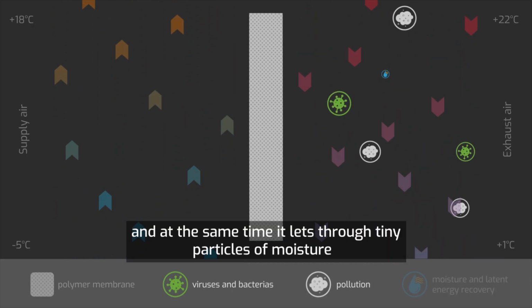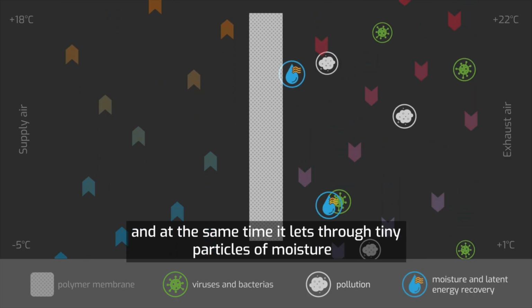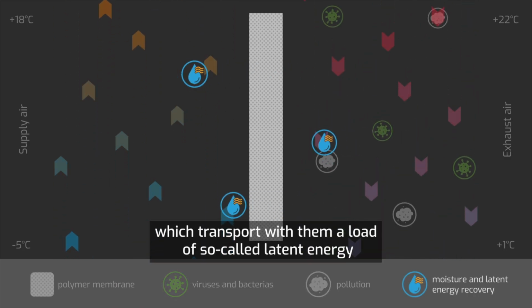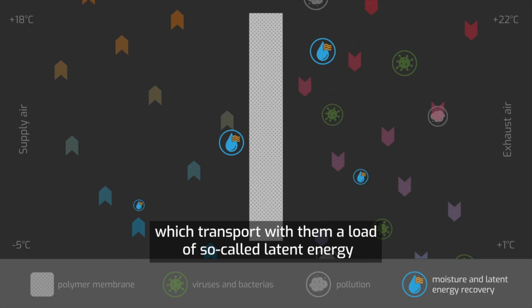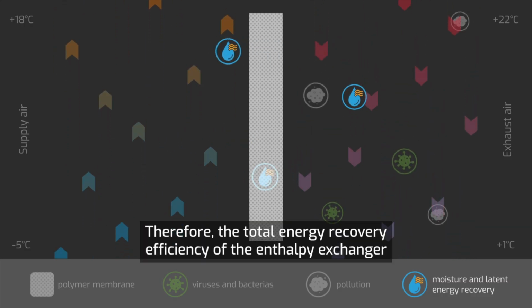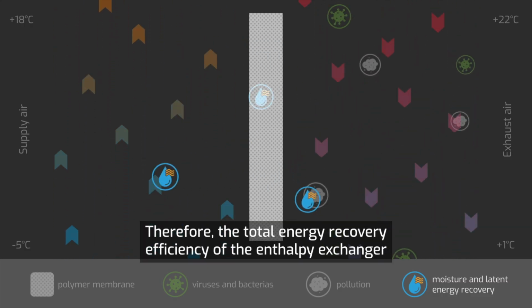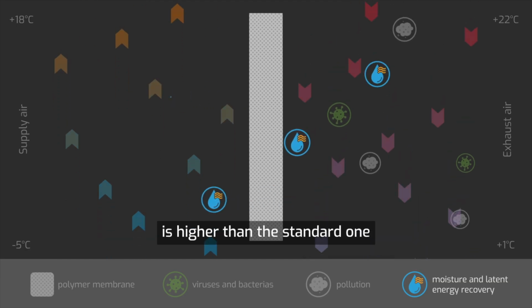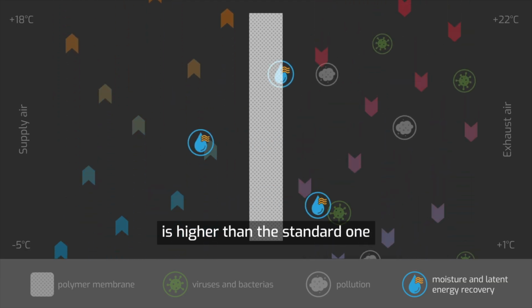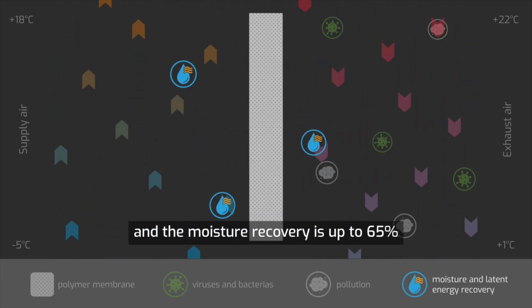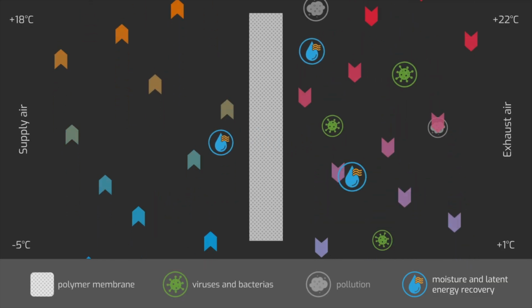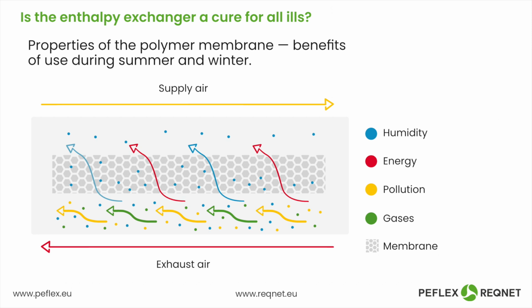And at the same time, it lets through tiny particles of moisture, which transport with them a load of so-called latent energy. Therefore, the total energy recovery efficiency of the enthalpy exchanger is higher than the standard one, and the moisture recovery is up to 65%. The enthalpy exchanger is a cure for all ills. The enthalpy exchanger is a solution to problems such as excessively low air humidity during the winter season.